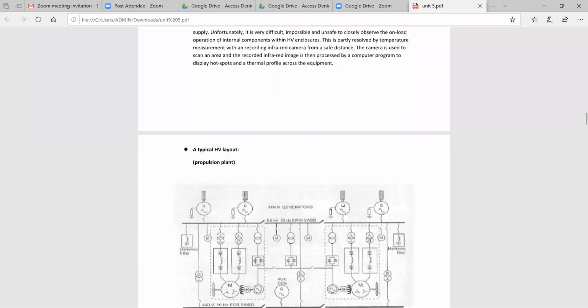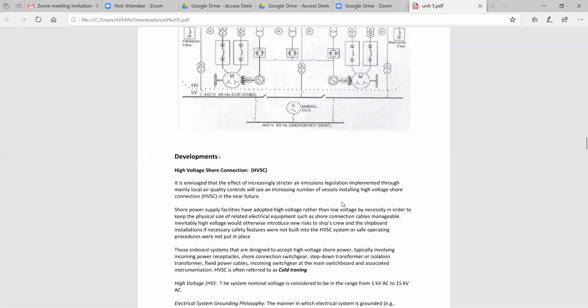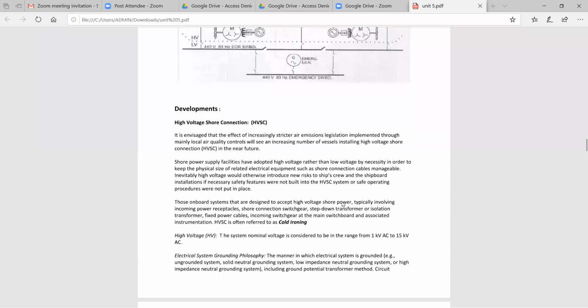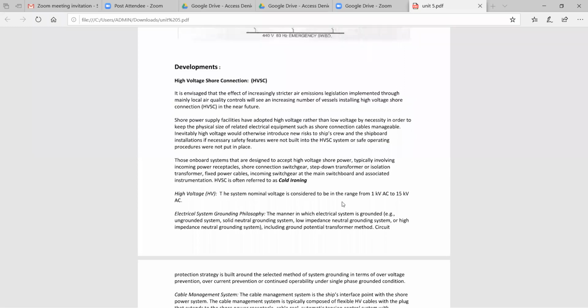In this safety, we have a typical layout of a propulsion system. That means the development of high voltage shore connection, simply mentioned as HVSC, high voltage shore connection. The high voltage shore connection should be very simple. That means you have a ship as well as a shore. How should the electricity be transferred from ship to shore, or from shore to ship? These high voltages are considered at 1 kV AC to 15 kV AC, that means 1 kilovolt alternating current to 15 kilovolt alternating current system.